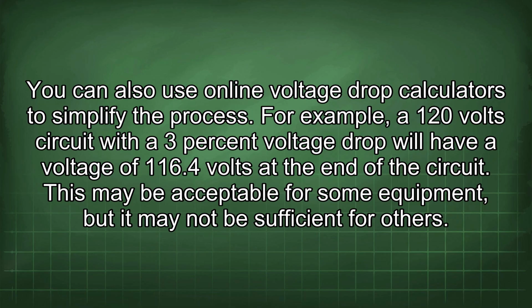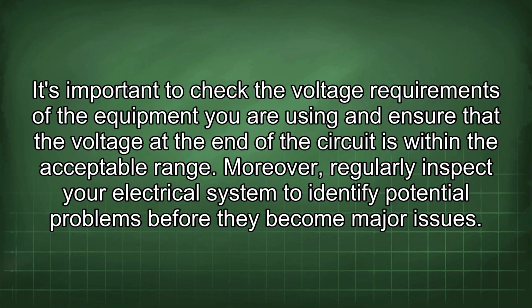For example, a 120-volt circuit with a 3% voltage drop will have a voltage of 116.4 volts at the end of the circuit. This may be acceptable for some equipment, but it may not be sufficient for others. It's important to check the voltage requirements of the equipment you are using and ensure that the voltage at the end of the circuit is within the acceptable range.